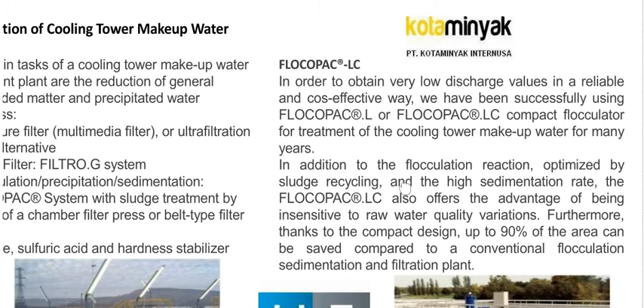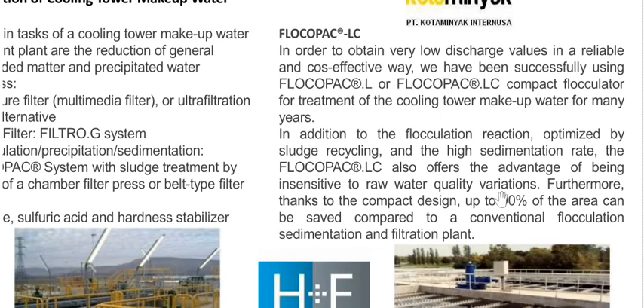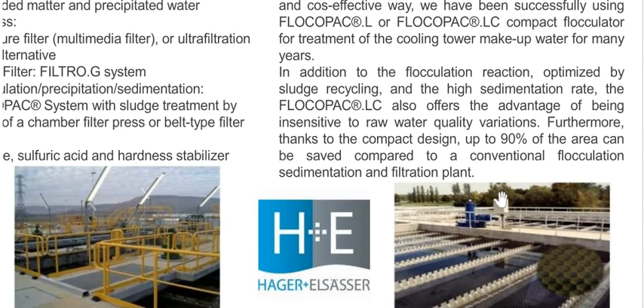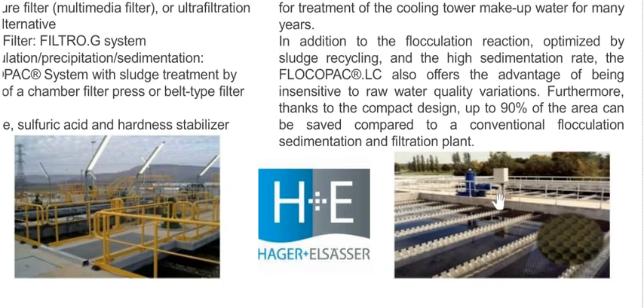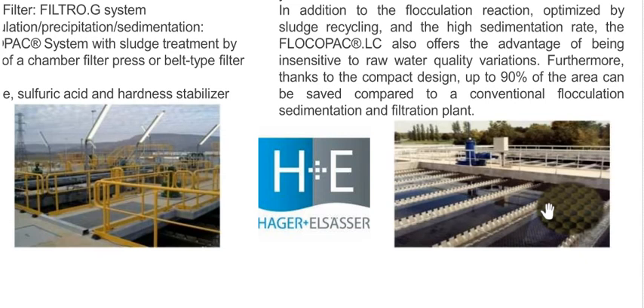Flocopac. In order to obtain very low discharge values in a reliable and cost-effective way, we have been successfully using Flocopac L or Flocopac LC, a compact flocculator, for treatment of the cooling tower makeup water for many years. In addition to the flocculation reaction optimized by sludge recycling and the high sedimentation rate, the Flocopac LC also offers the advantage of being insensitive to raw water quality variations. Furthermore, thanks to the compact design, up to 90% of the area can be saved compared to a conventional flocculation, sedimentation, and filtration plant. So this is an example of the H+E installation for water treatment.